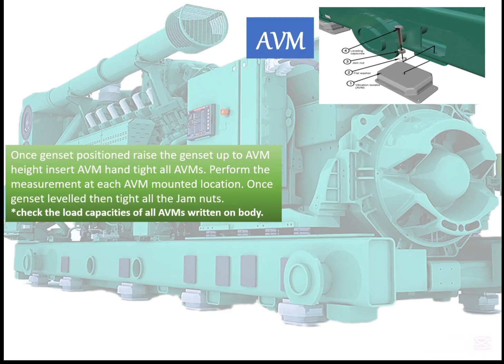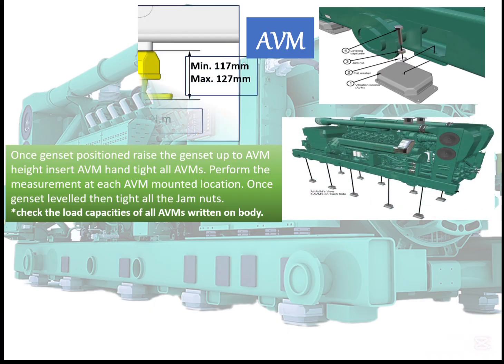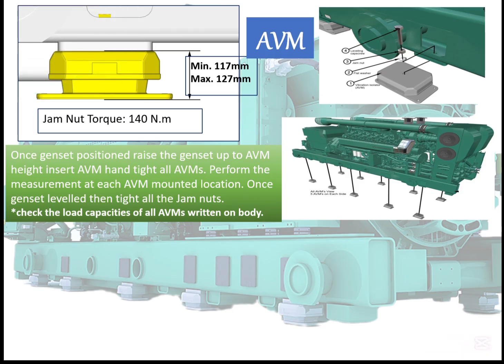Once the genset is positioned, raise the genset up to AVM height. This can be achieved through monkey jacks or hydraulic jacks. Insert the AVMs and tighten all the AVMs. Then perform the measurement on each AVM. This is the AVM. Look at the measurements, which should be between the minimum and maximum, and the torque of the jam nut. Once we hand tighten them, we should take the measurements. If within this range, then we use the plumb on the HDM of the genset. If it's level, we can now tighten all the AVMs.